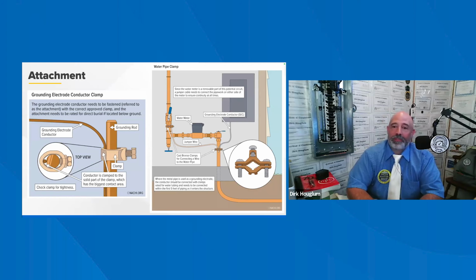metal water pipe in a house was the most common type of grounding at the time. The right image shows the cast bronze clamp for connecting the wire to the water pipe. Where the metal pipe is used as a grounding electrode, the conductor should be connected with clamps rated for water tubing and needs to be connected within the first 5 feet of piping as it enters the structure. Since the water meter is a removable part of the potential circuit, a jumper cable must be attached on either side of the meter, so that way if it does get energized, it's not going to blow out that meter either.